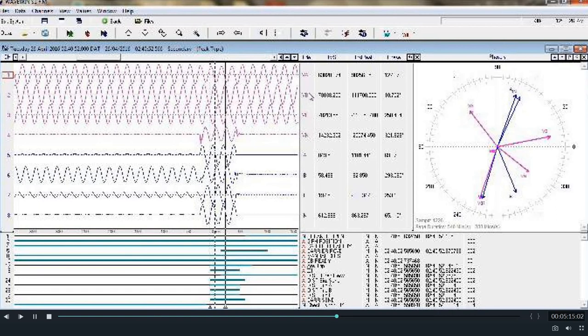Similarly, we will be able to observe in the digital channels that there was a command of circuit breaker open. Because of that, after this command, the circuit breaker was opened. When the circuit breaker was opened, immediately the current became 0. That's why the spikes in the current graph have reduced and it has come down to almost 0.